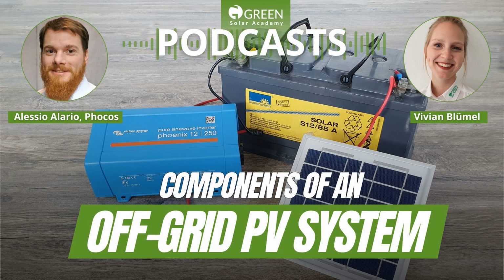I would say it depends. I would say that definitely the advantages we've just discussed are lower cost, ease of use and ease of installation. I think what still speaks for individual components, so a charge controller and inverter separately, is if you have a big mismatch between the AC power that you need and the PV power that you have. So for example, you might have a very big load, which is only running a few minutes a day, maybe a big pump or something like that. And that means you don't need a huge PV array. You might just need a few hundred watts, even though the load might be a 5 kilowatt load.